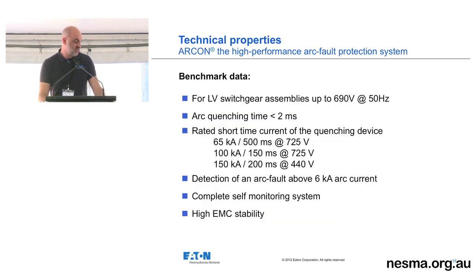Here's some of the major statistics. So it's for switchgear assemblies up to 690 volt. The time there is the critical factor. It's under 2 milliseconds. There's nothing that's faster on this planet that will provide you this solution. The rated short circuit times, it goes from 65 up to 150 kA for all those ratings you see there. It's complete self-monitoring, as I stated before, and it's also EMC compatible. So part of the verification now is to have EMC compliant product within the switchboard, so it meets that compliance as well.